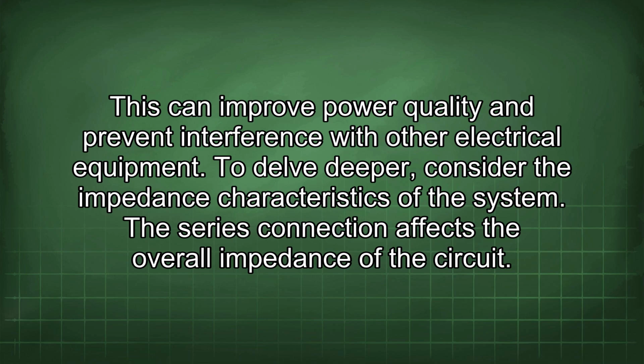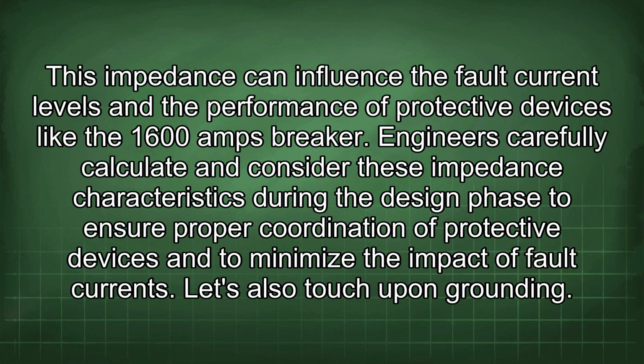To delve deeper, consider the impedance characteristics of the system. The series connection affects the overall impedance of the circuit. This impedance can influence the fault current levels and the performance of protective devices like the 1600 amps breaker. Engineers carefully calculate and consider these impedance characteristics during the design phase to ensure proper coordination of protective devices and to minimize the impact of fault currents.